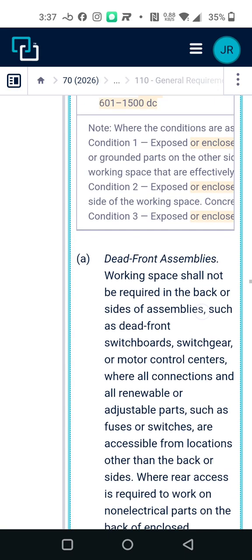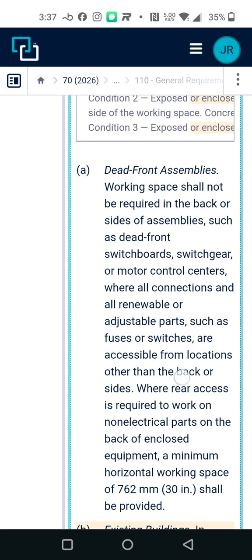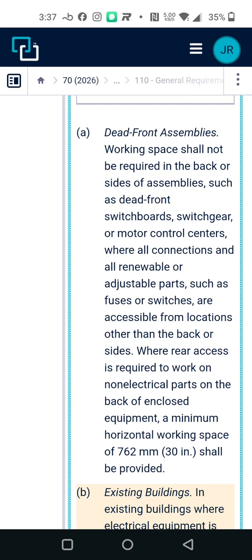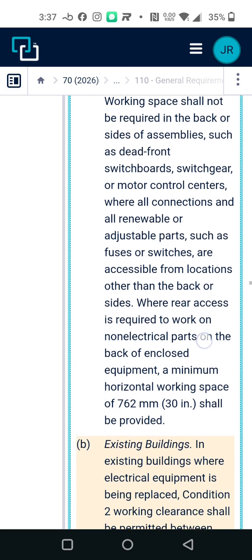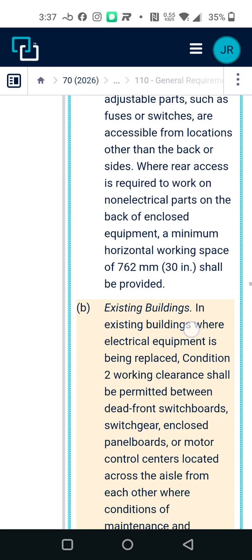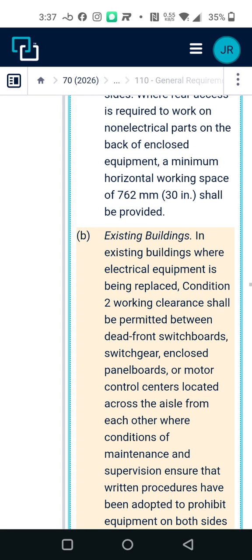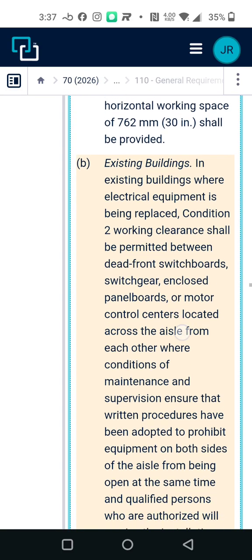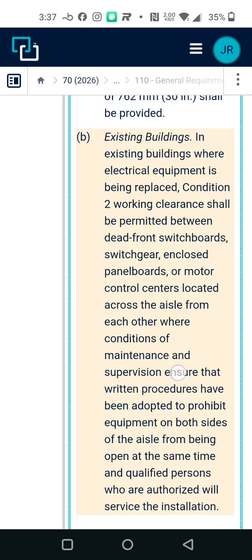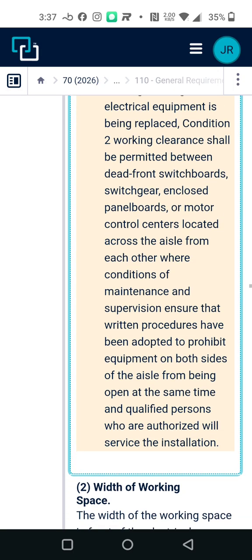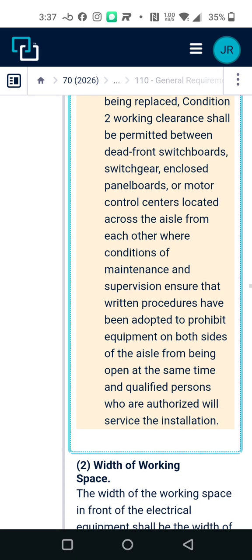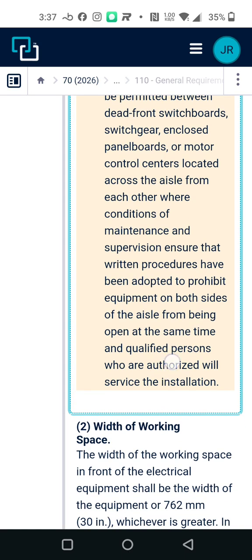Alright, dead front assemblies. Working space should not be required in the back or sides of assemblies, such as dead front switchboards, switchgear, motor control centers. Okay, I'm gonna go through this. Existing buildings. In existing buildings, when electrical equipment is being replaced, condition 2 working clearance should be permitted between dead front switchboards, switchgear, panelboards, or motor control centers located across the aisle from each other.